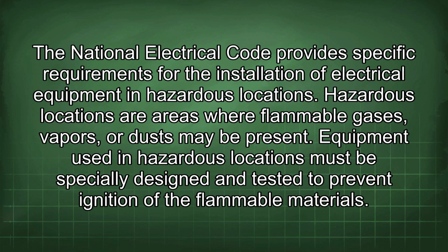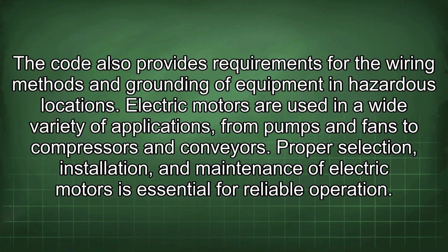The National Electrical Code provides specific requirements for the installation of electrical equipment in hazardous locations. Hazardous locations are areas where flammable gases, vapors, or dust may be present. Equipment used in hazardous locations must be specially designed and tested to prevent ignition of the flammable materials. The code also provides requirements for the wiring methods and grounding of equipment in hazardous locations.